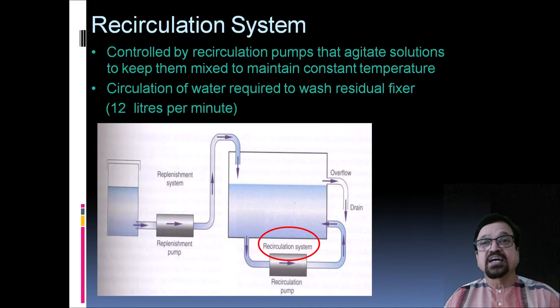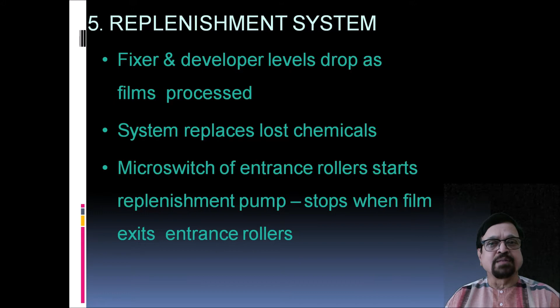Now, replenishment system. Fixer and developer levels drop as the film is processed. As we have already seen, when films are passing, the developer receives a dry film and lets out a wet film, so some water and chemicals go with the film. The replenishment system replaces the lost chemicals. Whatever chemicals are drained with the film are re-put, with the help of a pump, into the respective tank and the levels are maintained.